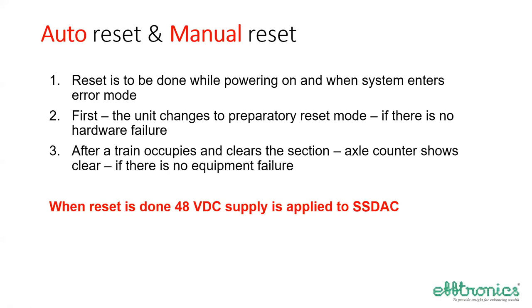Because we are monitoring the same section by two processor-based systems, it is possible to provide auto reset. So there is a facility for both auto reset as well as a manual reset. Auto reset is carried out at the equipment level itself, whereas manual reset still remains with the station master. As we have already seen, when reset is done, 48 volt DC supply is applied to the SSDAC.